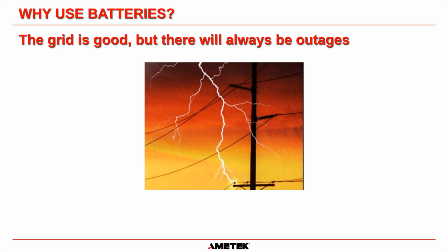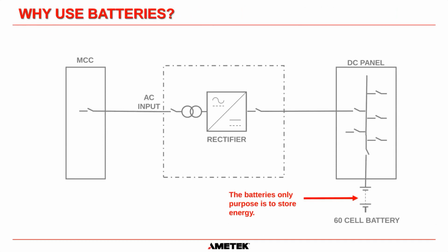So the grid is good, but there will always be power outages. You know, the grid in the US is usually very reliable. But somebody in your local neighborhood, a big truck can run into a power pole, knock down part of the system, and you're going to lose power to your facility in some circumstances. So you cannot rule out that there will be power outages, sags, surges, or anything like that. So that's why we use batteries. The batteries' only purpose is to store electrical energy. So if there is a power outage, it is then available to maintain the circuits connected. Okay.